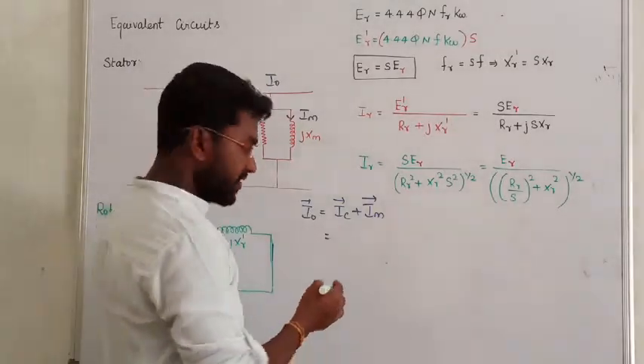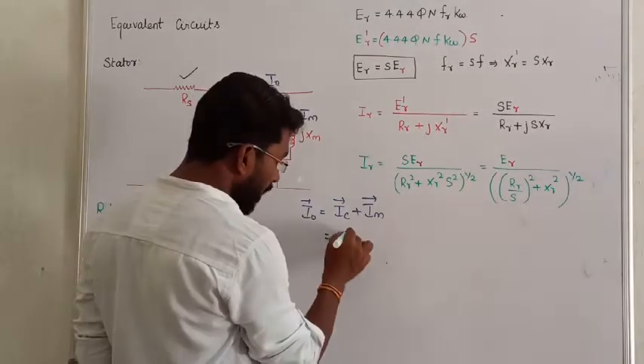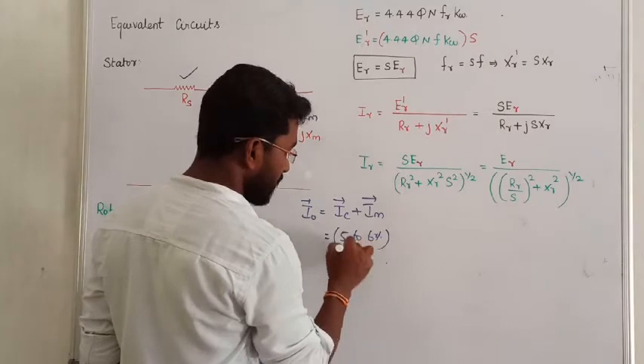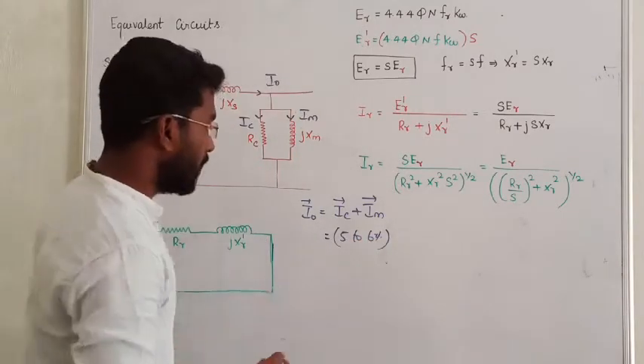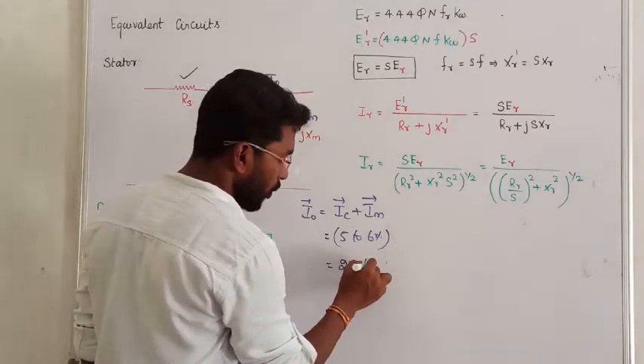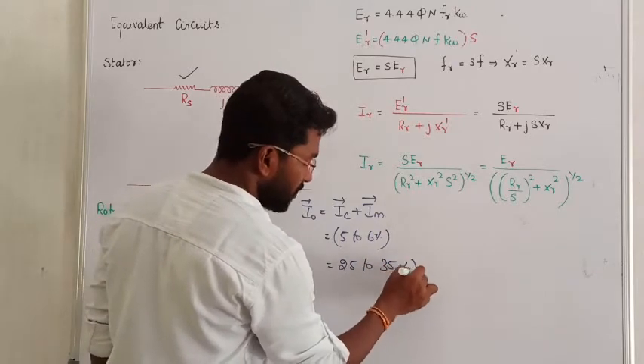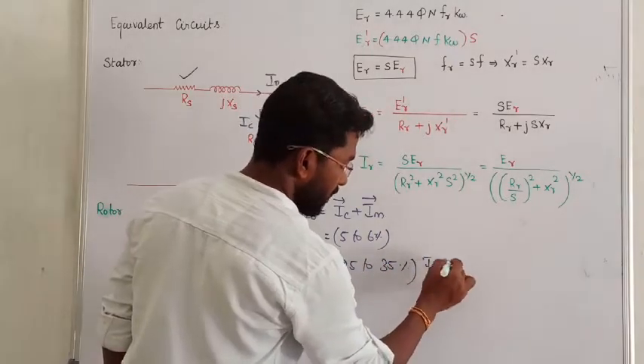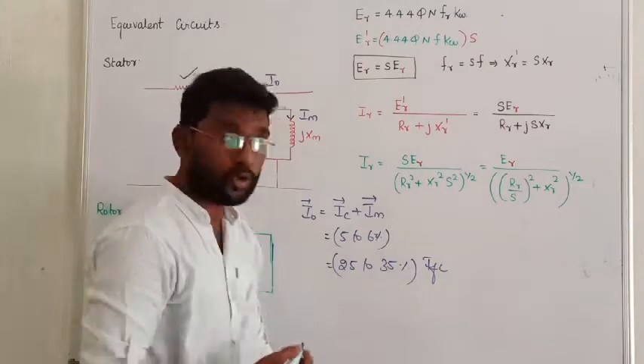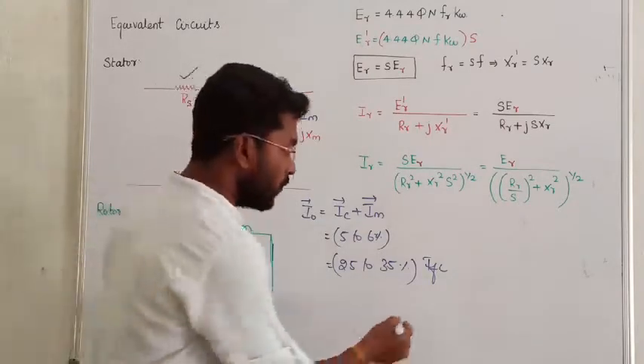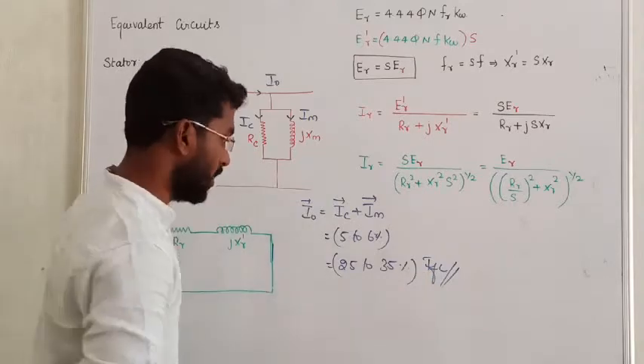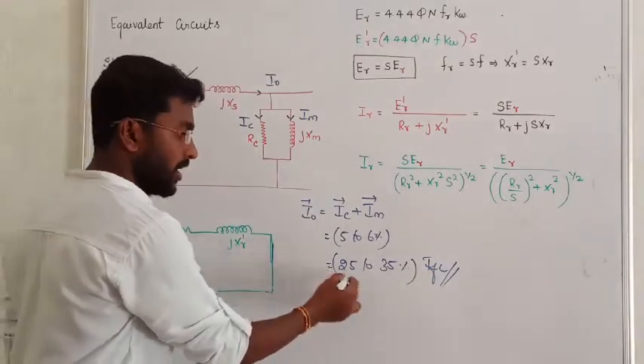The no-load current in a transformer is only 5 to 6 percent of full load current. But in case of an induction machine, it is going from 25 percent to 35 percent of full load current. So the no-load current component should equal 25% to 35% of full load current in case of an induction machine — don't forget that. No-load current is very high.